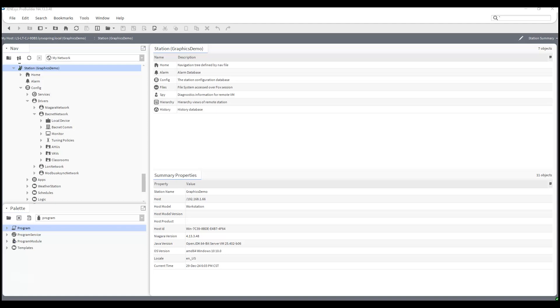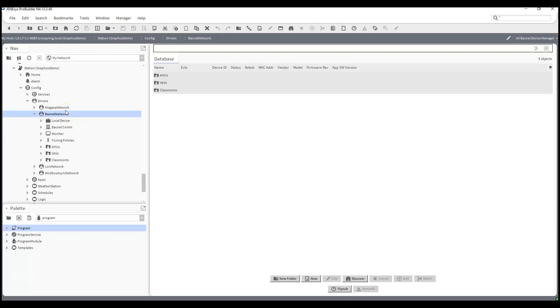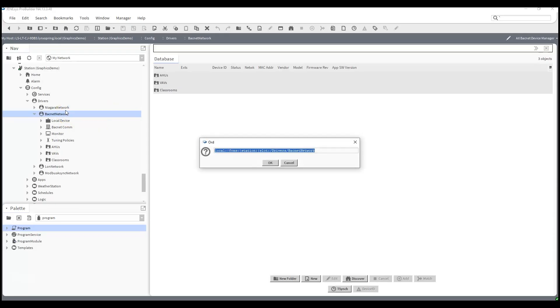The first thing I want to do is open up an ORD. To do that I can go to File > Open, or I can just hit Ctrl+L wherever I am. With Ctrl+L you can see there's already an ORD in here from something I previously clicked on. Let's get rid of the drivers/bacnet portion and start fresh. I'm going to do a BQL select — for that I need my pipe character, that straight line, followed by bql: and then select.